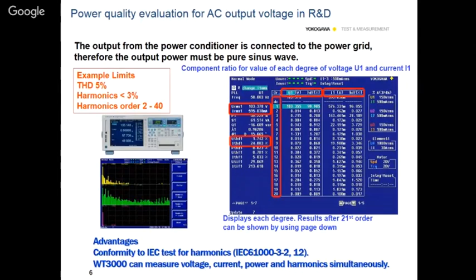There are equipments available that can measure either the normal voltage, current, power and frequency, or only harmonics, but simultaneous measurement of both is not possible. The WT3000 can measure both simultaneously: total active power, fundamental active power from the harmonics measurement, and fundamental reactive power from the harmonics measurement. If you remember this table, the one represents the fundamental harmonics, so that is what we are talking about here: the fundamental active power and the fundamental reactive power.